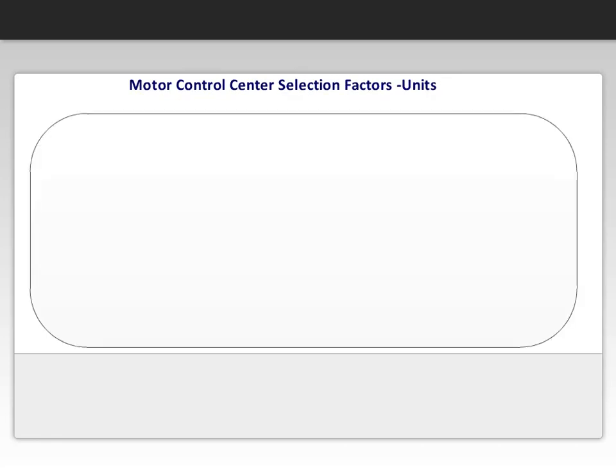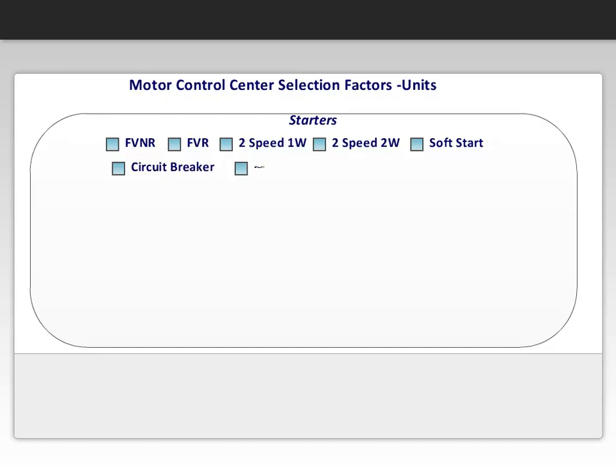Now we'll take a look at the selection factors for Motor Control Center units that are starters. We need to know whether it's going to be a full voltage non-reversing or a full voltage reversing, if it's going to be a 2-speed, and if it's going to be a 2-speed 1-winding or 2-speed 2-winding, if a soft start is required, and what type of disconnect does the customer want ahead of this starter?